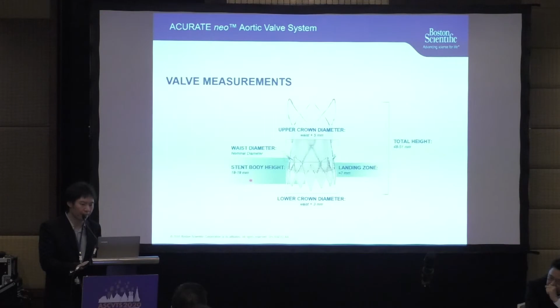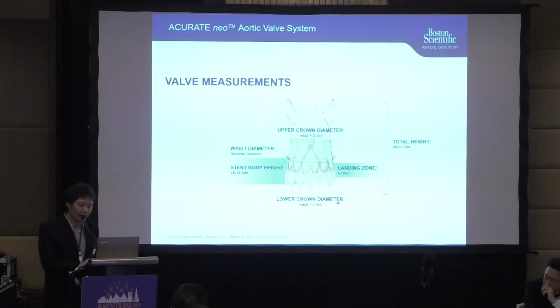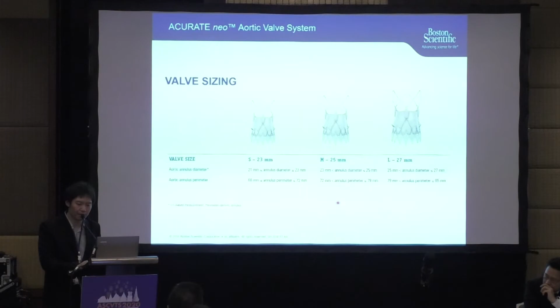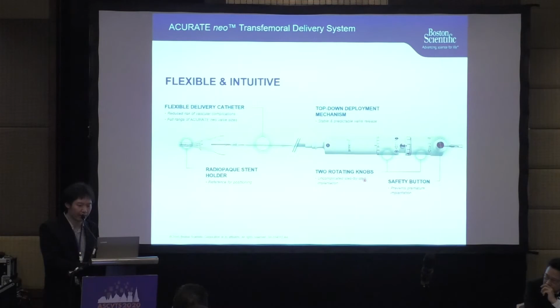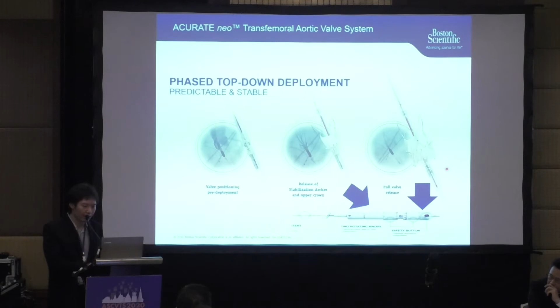So stent body height is around 18 to 19 mm. Landing zone is approximately 20 mm. Because the stent body height is quite narrow, coronary height more than 8 mm is safe to use. The valve size ranges from 21 to 27 mm. The delivery catheter is quite flexible. So the first operator just grips the delivery system, and the second operator rotates knob 1 and then knob 2, and then the stent is deployed.